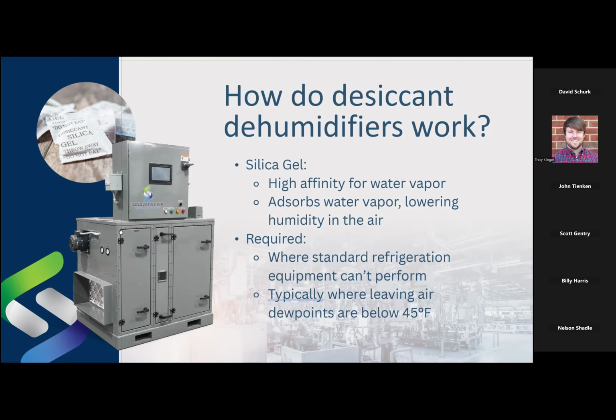And you could continue that process. Load it with moisture, stick it in the oven, heat it up, dry it out, take it out, use it again. Adsorbing moisture, high pressure to low pressure in the desiccant, desorbing moisture, high pressure in the desiccant, low vapor pressure in the air in the oven. And you have a continual cycle, right? But in practice, in the real world, in the field, that's a little cumbersome. Every time we load our desiccant up with moisture to pull it out and have to put it into an oven and heat it up and bring it back. So what we do is we put the oven in the unit. Simple. And we create a process that's continually adsorbing and desorbing moisture continuously.